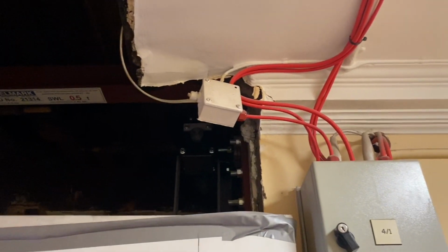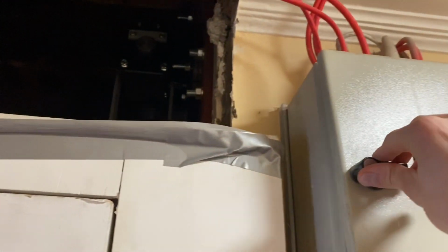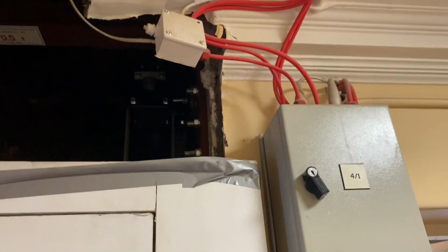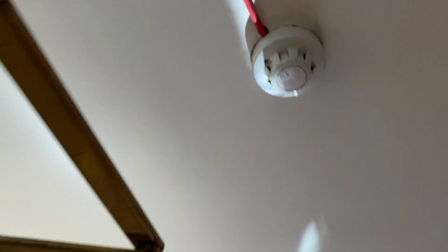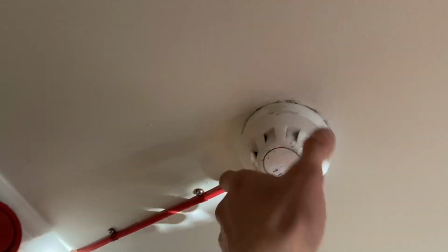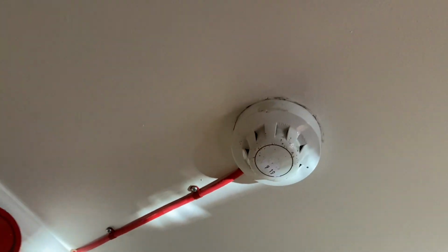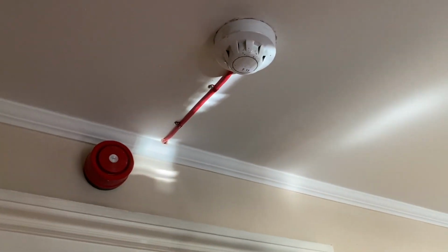Right, so come over here. Firstly, I thought there could be a problem in there. Again, it says detector removed, so no, it's not that. I had a look at everything, thinking could there be a detector inside there that's been disconnected, or a wire cut. I thought maybe that FP cable's been cut somewhere here as well, but nah, that's something else. Anyway, it's not in there. I walked into this room and this detector here was loose, it hadn't been tightened up properly. I tightened all the connections up, all sorted, customer's happy.